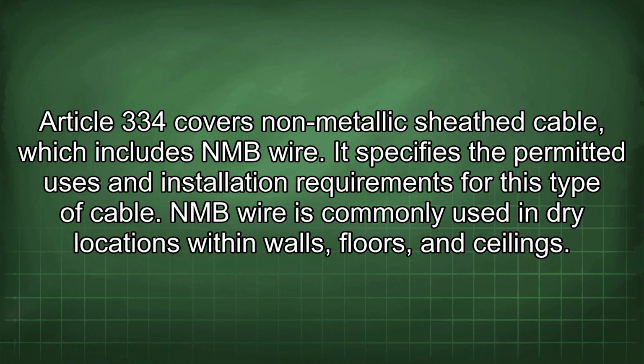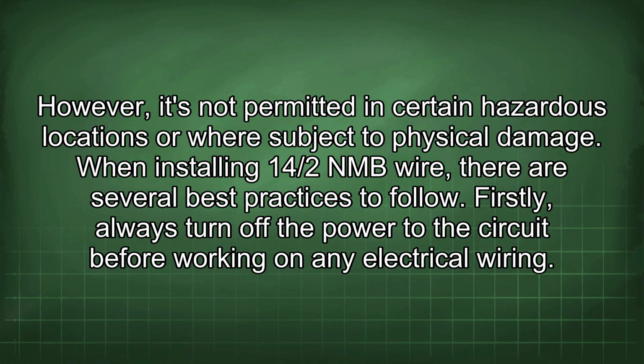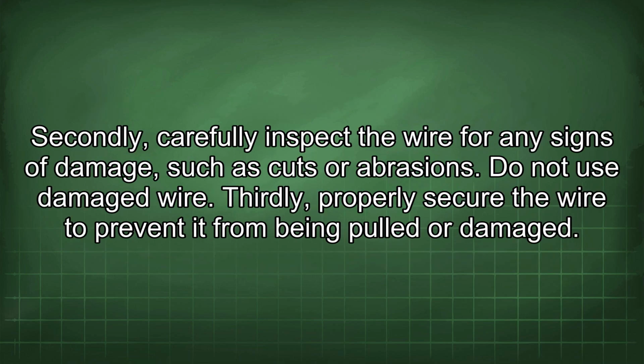Article 334 covers non-metallic sheath cable, which includes NMB wire. It specifies the permitted uses and installation requirements for this type of cable. NMB wire is commonly used in dry locations within walls, floors, and ceilings. However, it's not permitted in certain hazardous locations or where subject to physical damage. When installing 14/2 NMB wire, there are several best practices to follow. Firstly, always turn off the power to the circuit before working on any electrical wiring. Secondly, carefully inspect the wire for any signs of damage, such as cuts or abrasions. Do not use damaged wire.